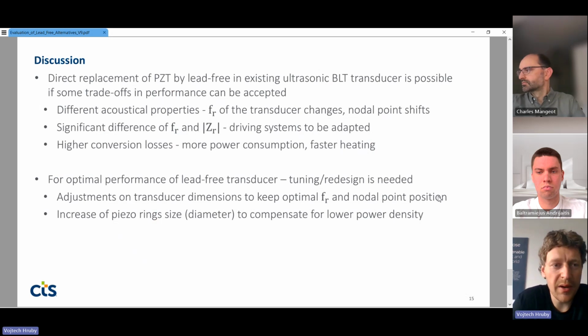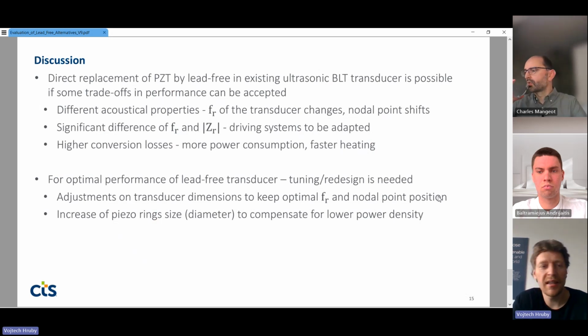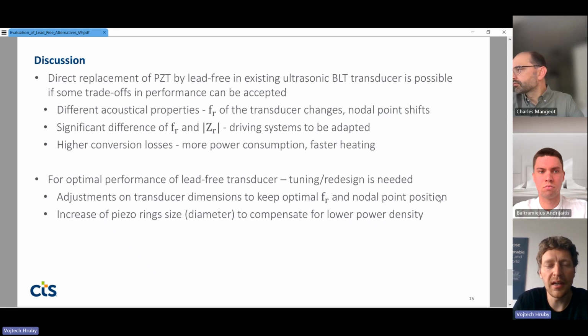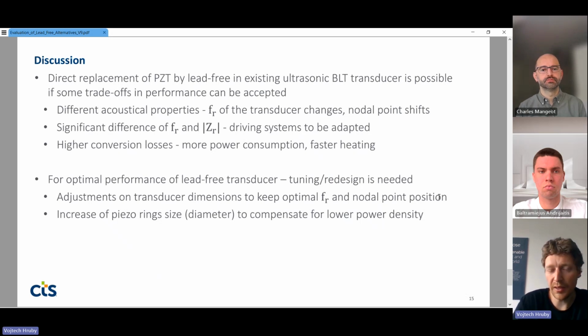So to discuss and summarize, we see that direct replacement of PZT by lead-free material in an existing ultrasonic bolted Langevin transducer is possible if some trade-offs in performance can be accepted. Due to the different acoustical properties of the lead-free materials when compared to PZT, the resonance frequency of the transducer changes and the nodal point also shifts. So this is important to consider.